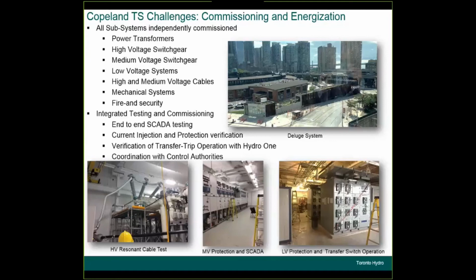One aspect of the design that is interesting is visible on the top right. When we got our final environmental assessment approval, we had a challenge because the initial design had a parapet wall between us and the wood construction roundhouse, and we were challenged that that is not consistent with the historical design and that we must have a continuous connection of our roof to the adjacent property. That introduced a hazard in that we could convey a fire to the adjacent roundhouse or vice versa. And the final solution to that was to install a dry sprinkler system as a deluge system to basically deluge the interface between the 2 buildings in the event of a fire.